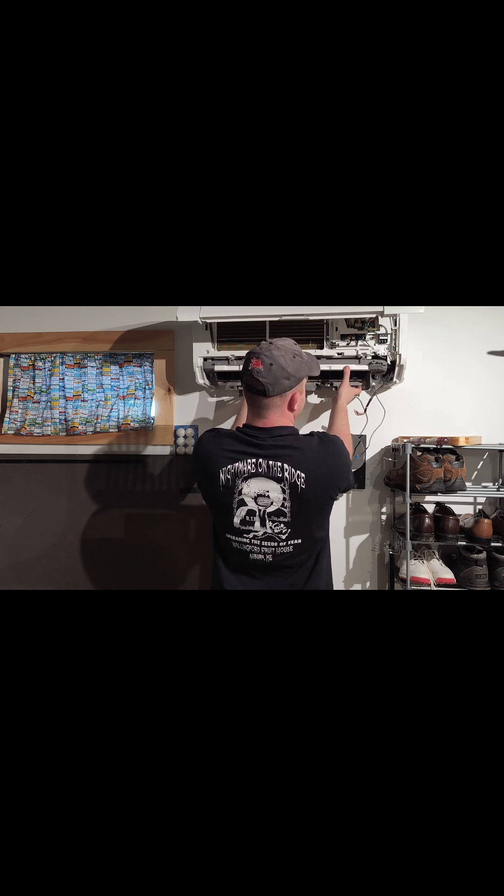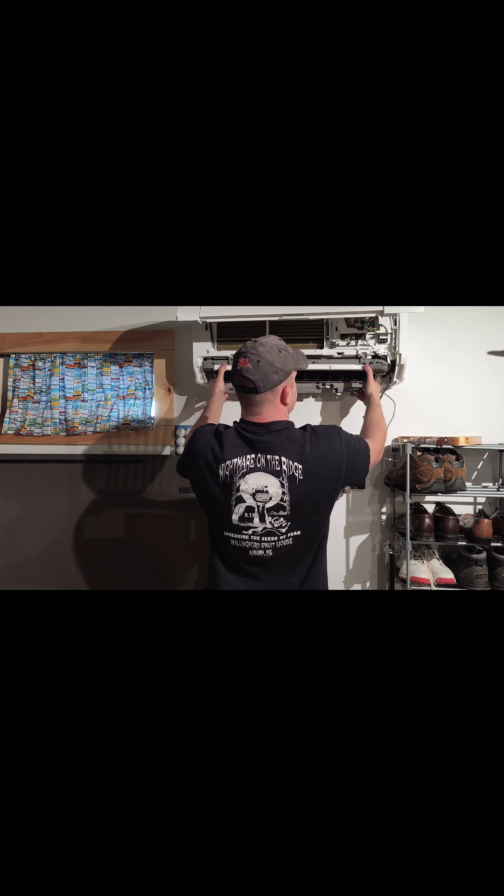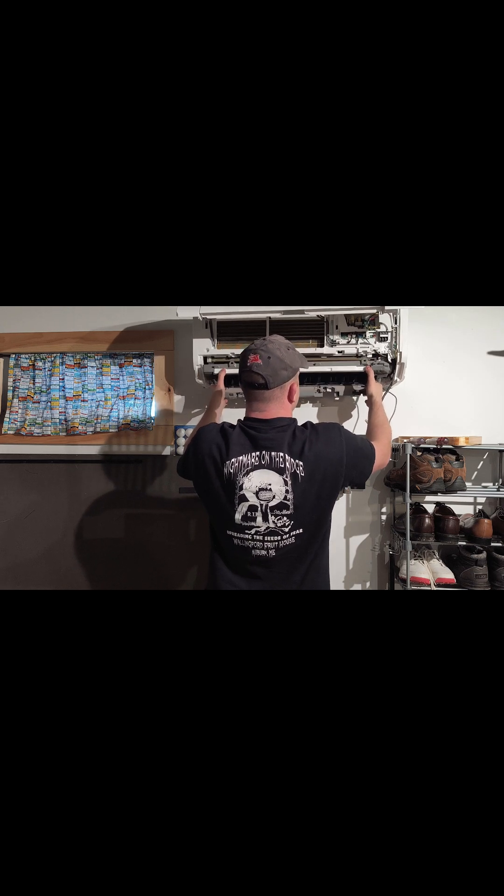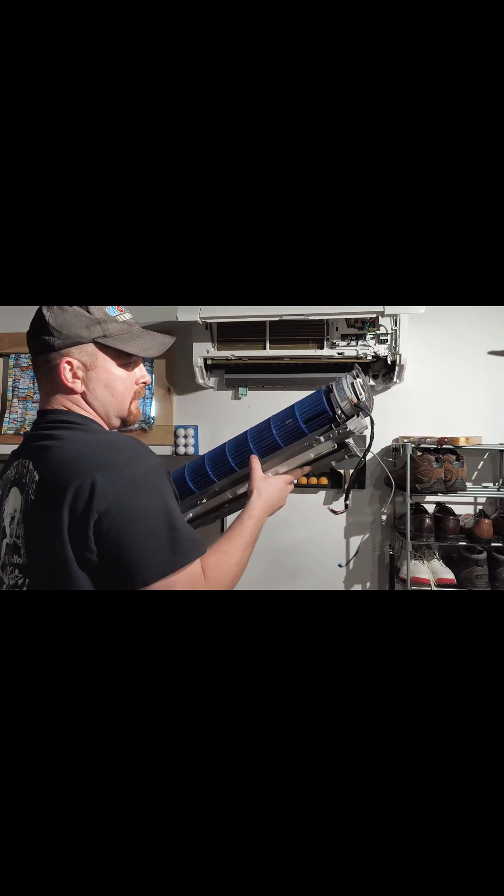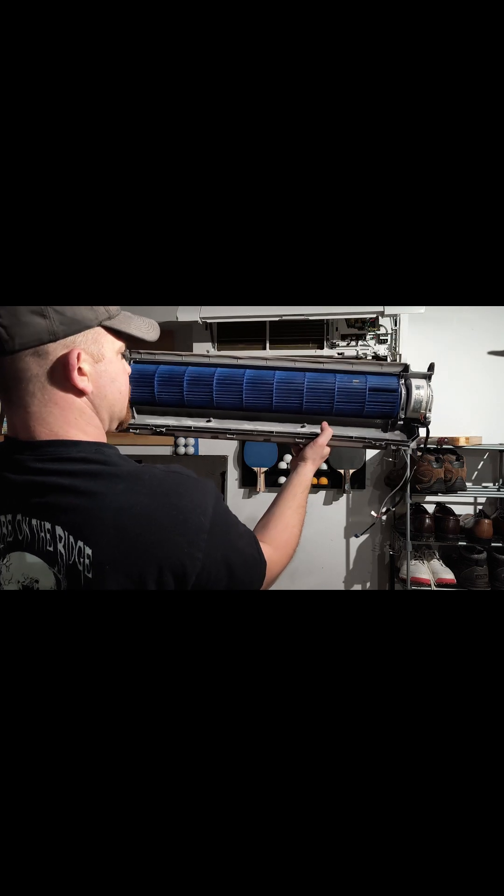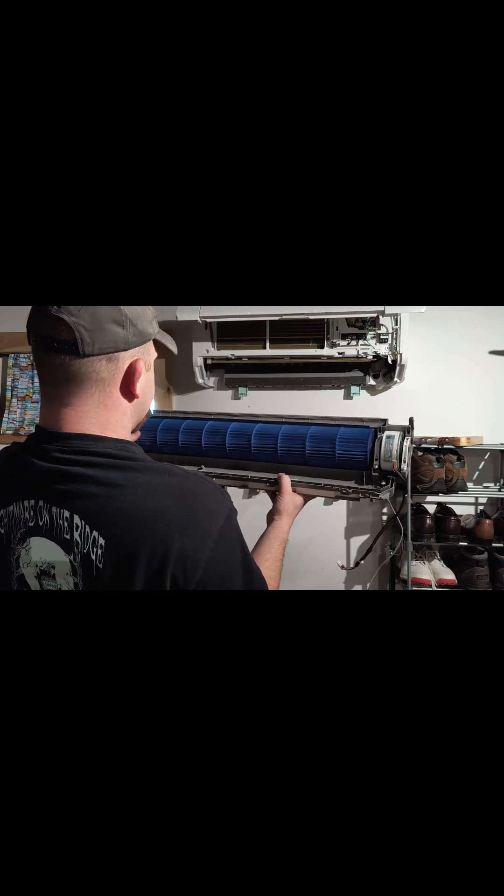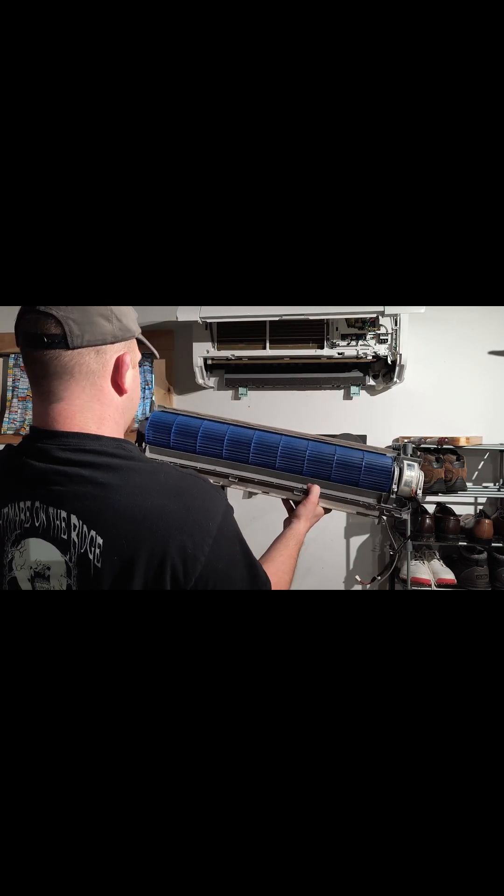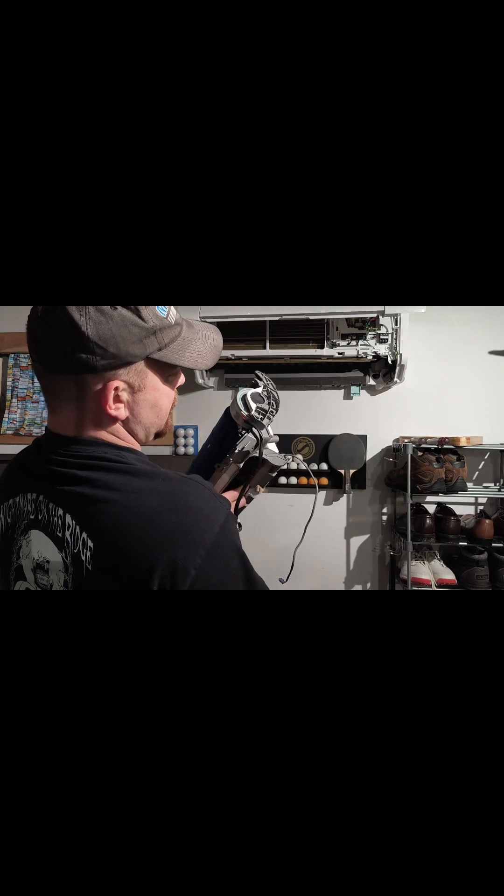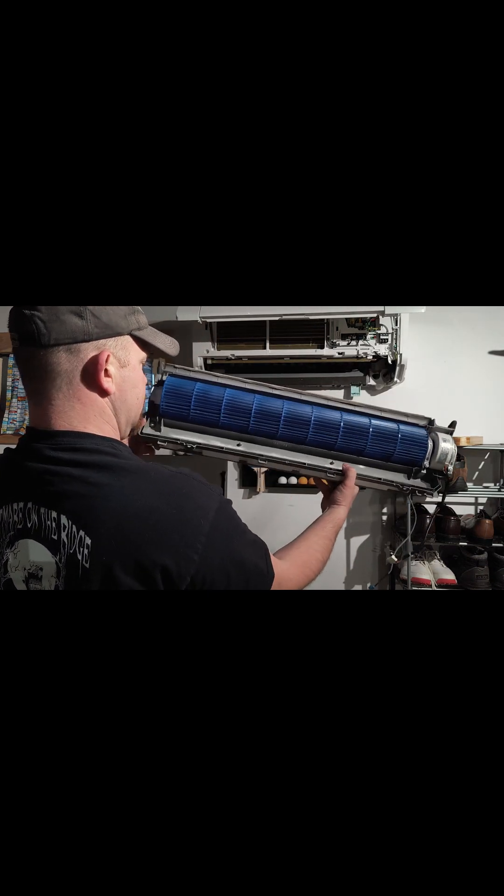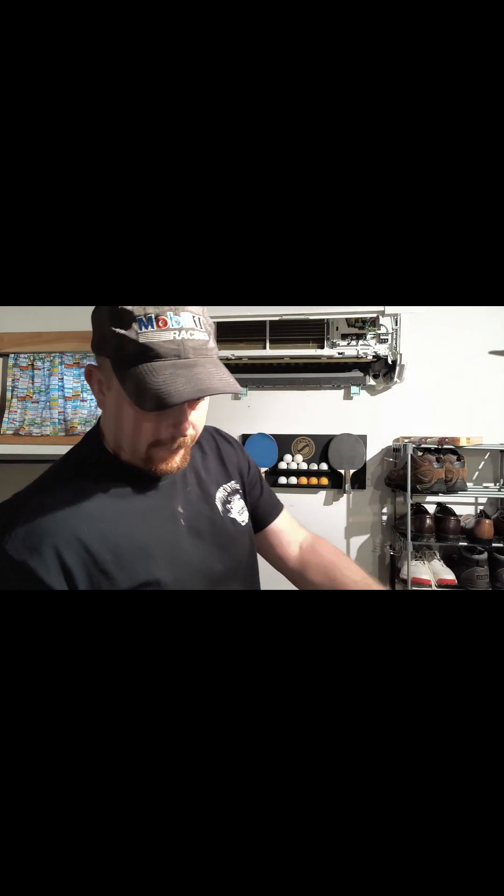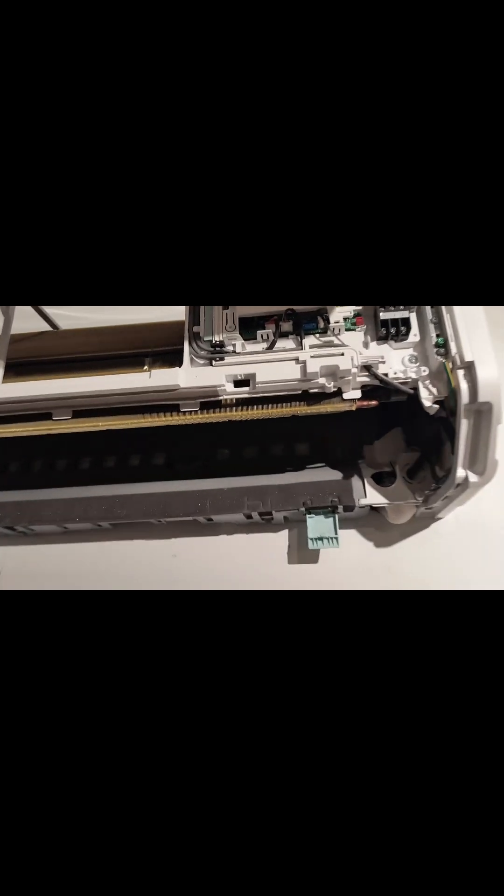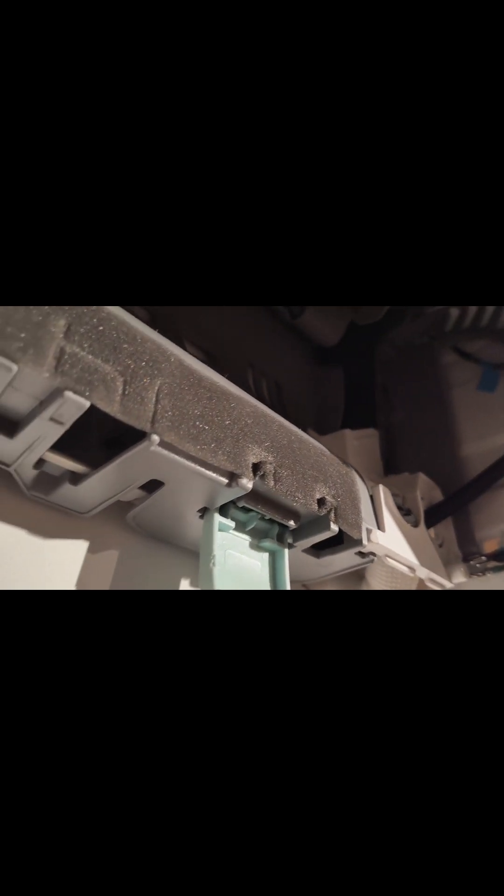Now you can see the whole thing's ready to come out, but the fan - if you kind of rock it a little bit carefully - the fan's kind of pushing up against the whole heat exchanger. So now the entire assembly that has the fan motor and the fan is out. This is also the whole drain pan where the condensate rains down from the evaporator in cooling mode. From here this whole thing could be taken apart and cleaned more thoroughly, or if you had a replacement fan or motor you'd plug it in here. Now with that out you can get a better look up into here. From here it's basically just that heat exchanger. This one looks very clean.